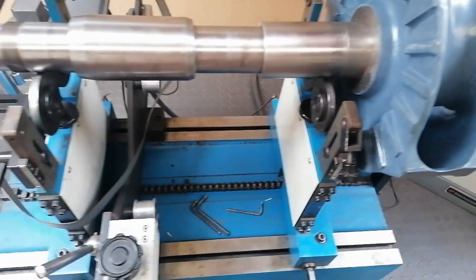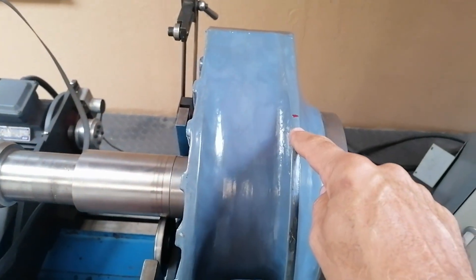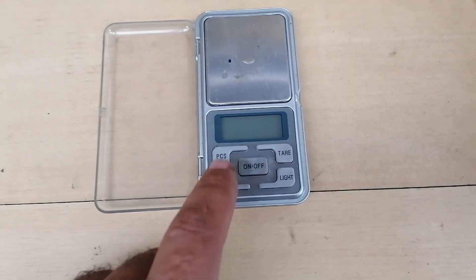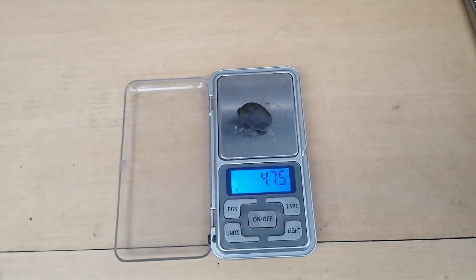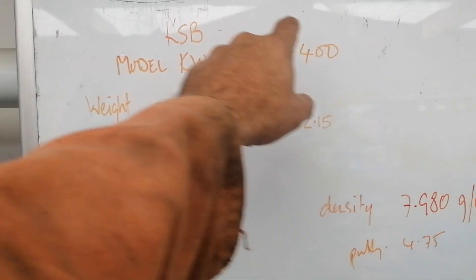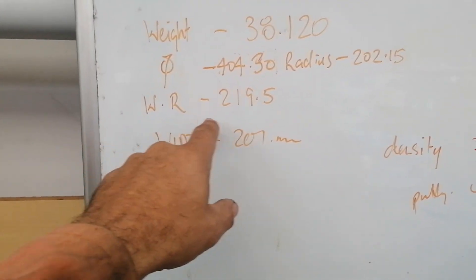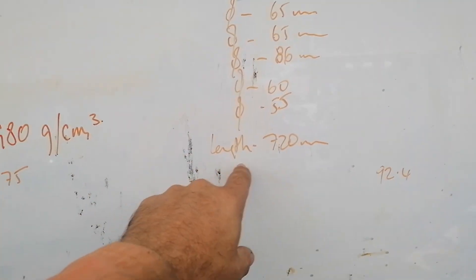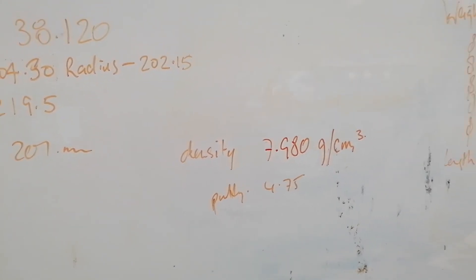Yes, she is most definitely heavy down here. Now I'm going to put the machine on and input all the data captured for this unit. This is the model of the pump - got the weight, the diameter, the radius, the wearing size, the width of the pump. I've got the shaft weight, the shaft diameter, the shaft length, and it's a cast iron unit so density is 7.980 grams per centimeter cubed, and the putty mass is 4.75.